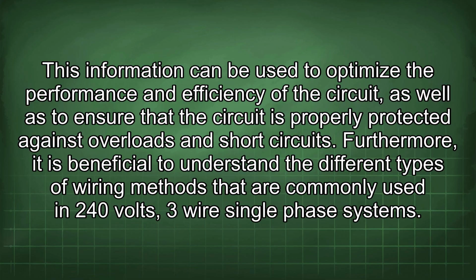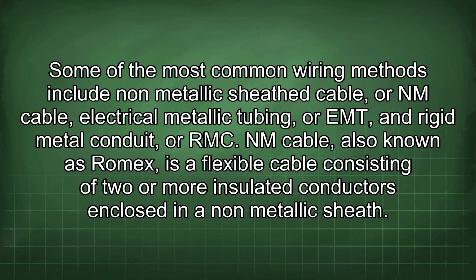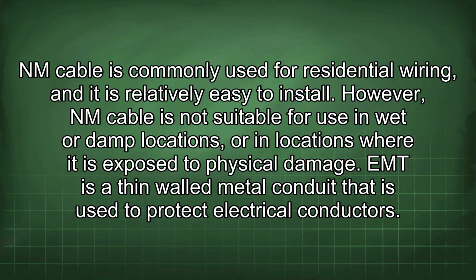Furthermore, it is beneficial to understand the different types of wiring methods that are commonly used in 240 volts, 3-wire single-phase systems. Some of the most common wiring methods include non-metallic sheathed cable or NM cable, electrical metallic tubing or EMT, and rigid metal conduit or RMC. NM cable, also known as Romex, is a flexible cable consisting of two or more insulated conductors enclosed in a non-metallic sheath. NM cable is commonly used for residential wiring and it is relatively easy to install.